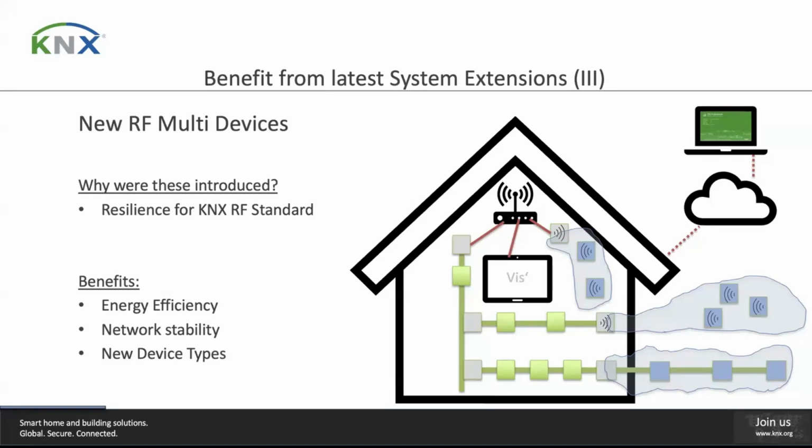It allows us to have really efficient devices where they don't need to do a lot of communication. For example, heating actuators that don't need lots of quick communication going on, but rely on batteries. Those can use the slow part of the multi-protocol, which enables long battery life. Or we can have devices that need quick, fast transmission and receiving of telegrams.